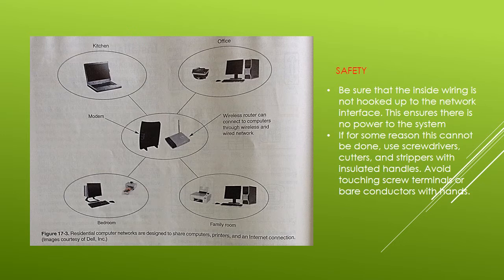Be sure that the inside wiring is not hooked to the network interface. This ensures there is no power in the system. If for some reason this cannot be done, use screwdrivers, cutters, and strippers with insulated handles. It is very preferable that they be high voltage insulation. Avoid touching screw terminals or bare conductors with your hands. Use care in drilling through walls, floors, or ceilings. Avoid areas where there may be electrical wiring, gas pipes, steam pipes, or water pipes. When working on existing telephone wiring, disconnect any transformer that might be supplying step-down voltage for dial lighting.